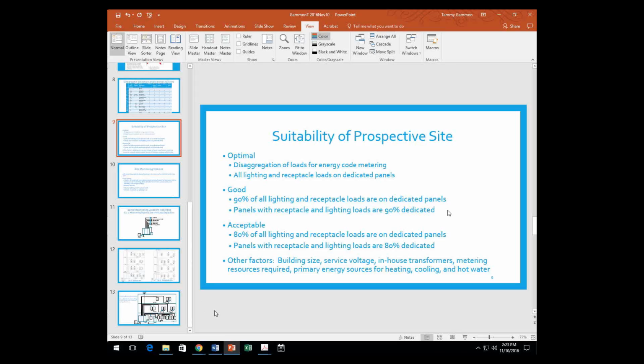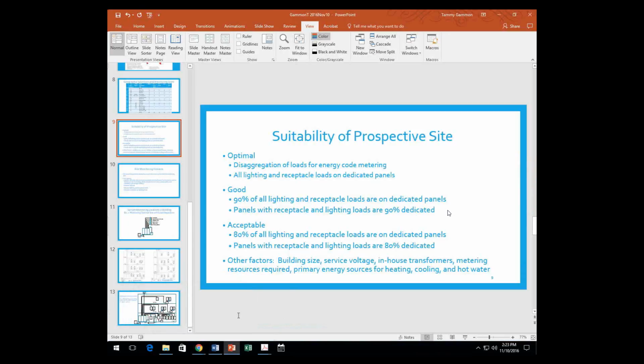That much said, Bob, what drives this is that even though you may have one space heater that keeps opening up a 20 amp breaker, say in one of those offices over here at Ohio State, even though that may occur to you, there's still a 300 kVA transformer in the electrical closet, and that thing has 3 kilowatts on it—because the National Electrical Code requires that it be specified at 300 kVA. Correct. So, I mean, that's a problem.